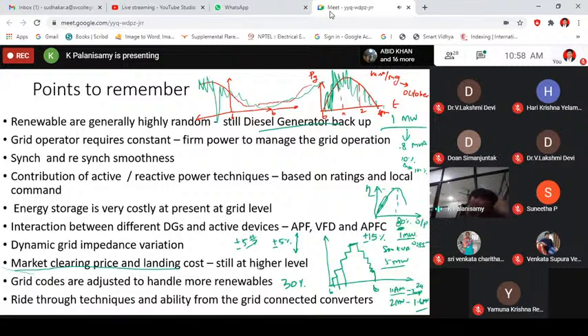See, when you are operating fully with conventional sources, that is, synchronous generators supplying the entire power, at that time the frequency limit was so strict. It means it is very narrow. It means 50: you can go 49.95 or you can go 50.05. Only that much level you have to maintain. But now most of the grid codes have adjusted themselves. Even the frequency can go plus 2 hertz or minus 2 hertz. It means I can operate from 52 to 48 hertz because of the highly random nature of renewables. So all the grid codes are adjusted, relaxed, to handle the renewables, right?